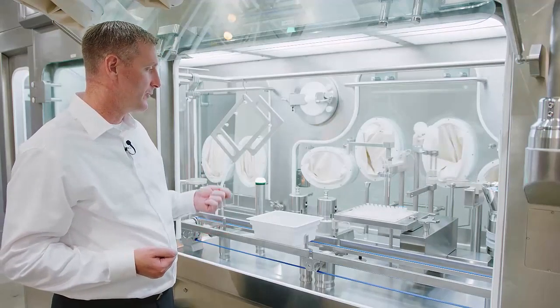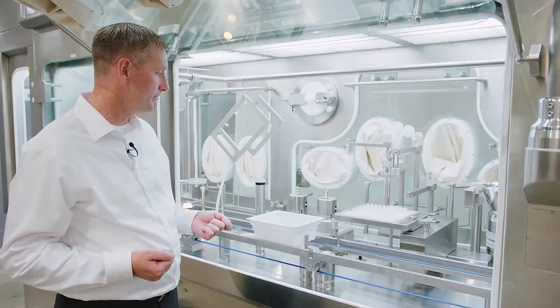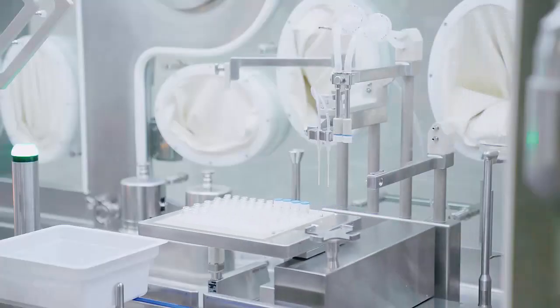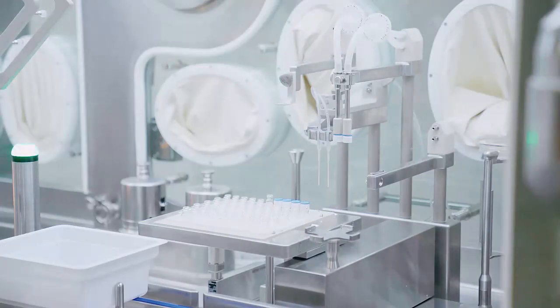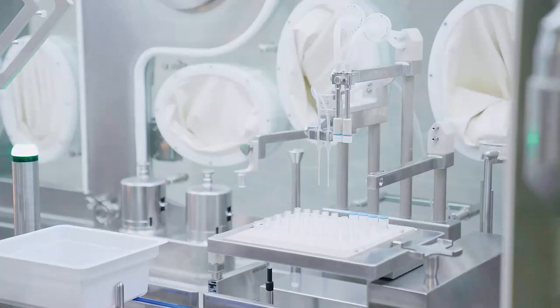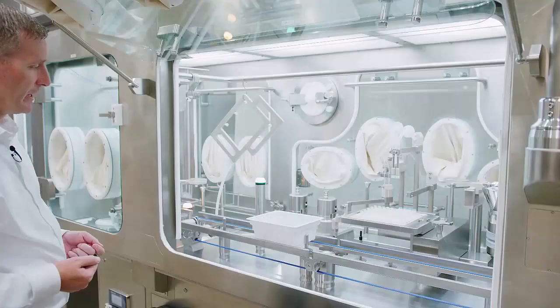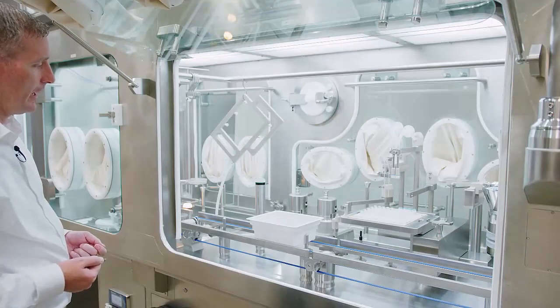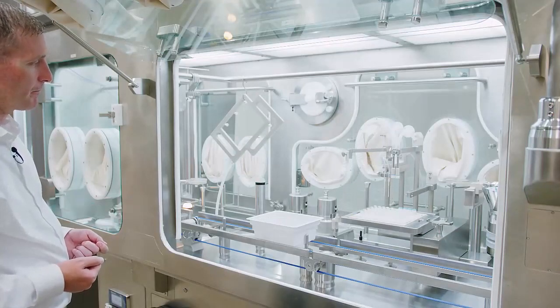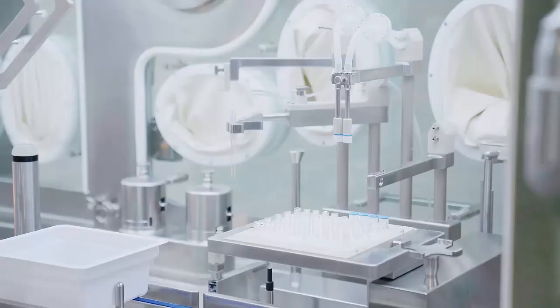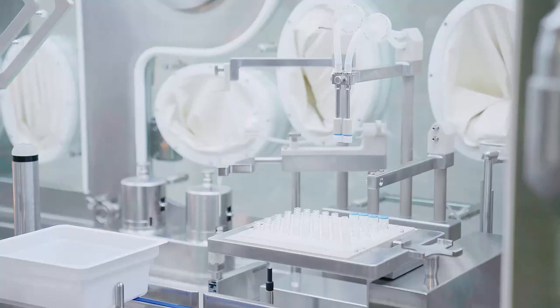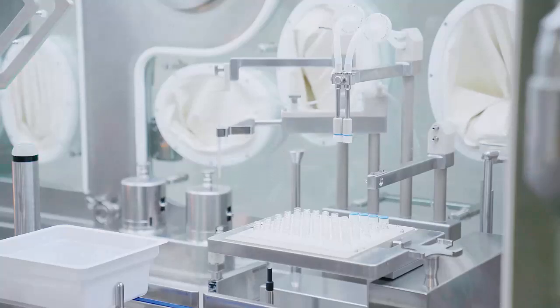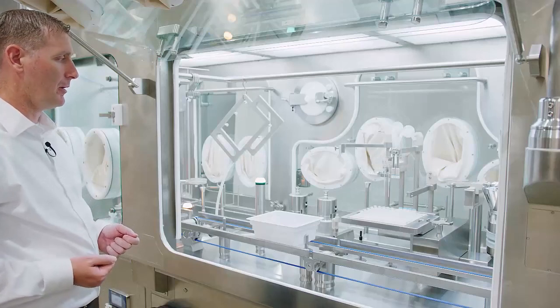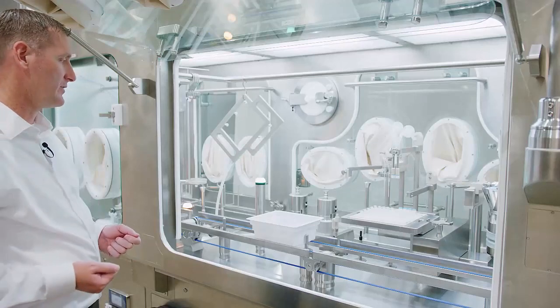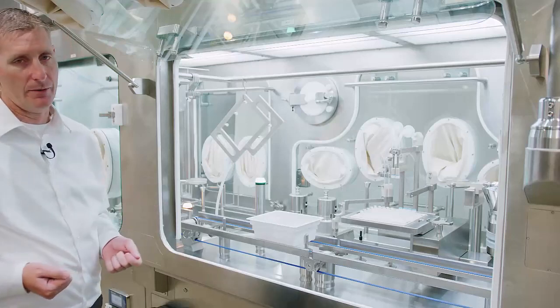Now that filling motion is fully programmable by the system. The system will actuate over. So what we're seeing now is the other arm is grabbing the vial. It's going to place it onto an IPC load cell. So this is a gravimetric balance, extremely accurate, and it's measuring the tare weight of the vial. And the fill nozzles will articulate over, dispense the drug product, and provide weight feedback directly to the system. So if the pump needs more calibration, has it drifted ever so slightly, this will provide that feedback automatically.